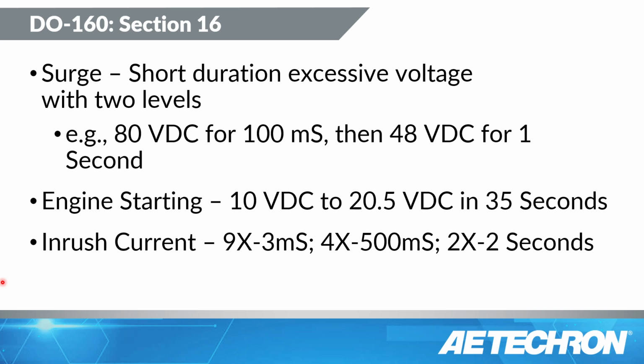Now, the inrush current test is really well done by the AE Techron system. The reason why is it gives you a very clean turn on without any overshoots or ringing or anything of that nature. In addition, you are allowed to have a ramp up during your inrush test.